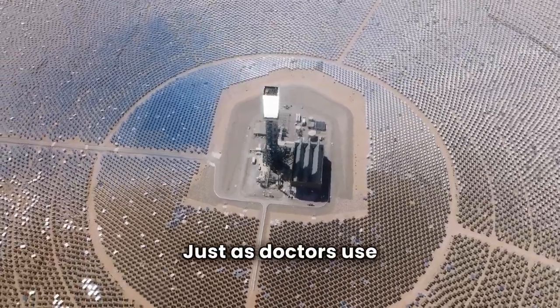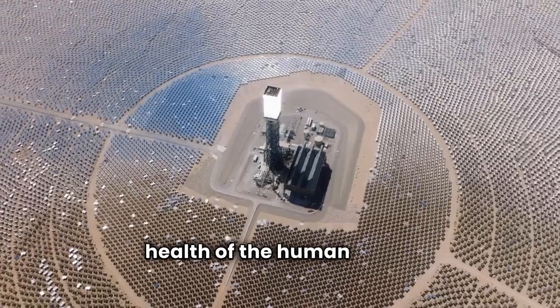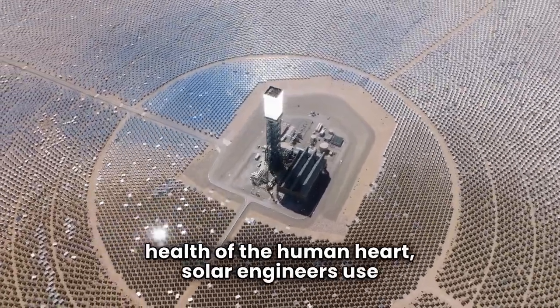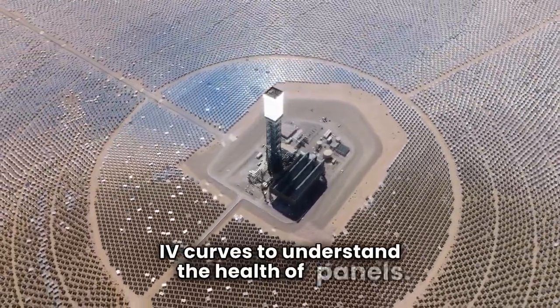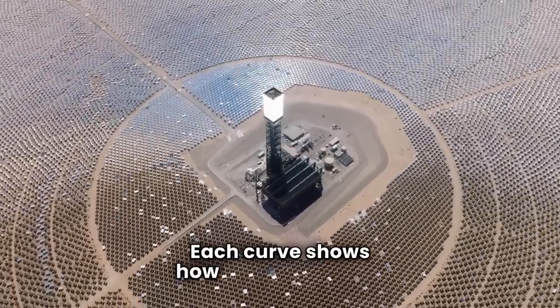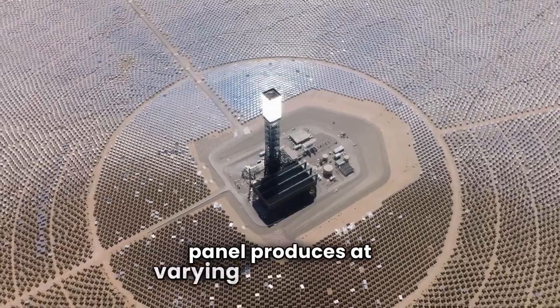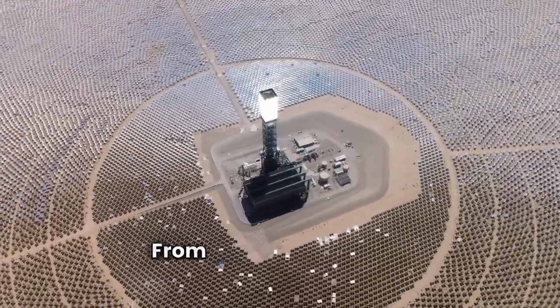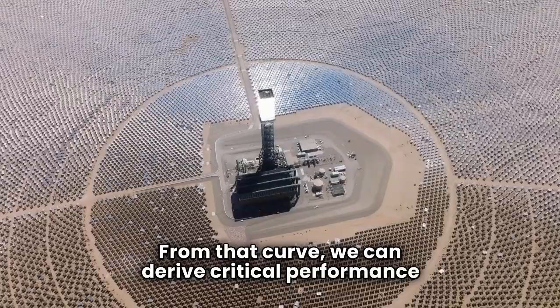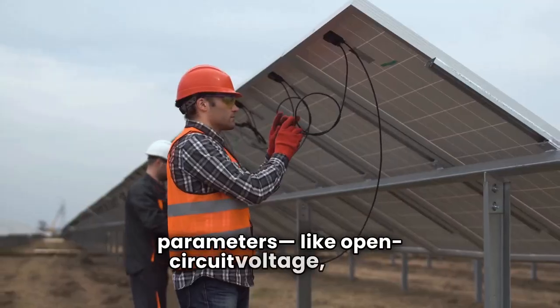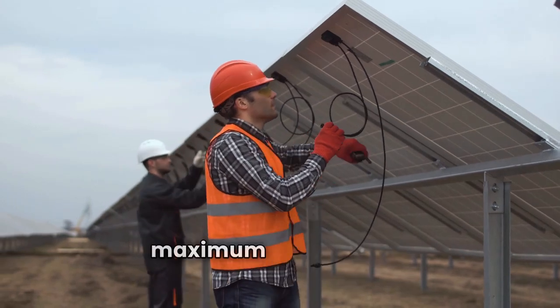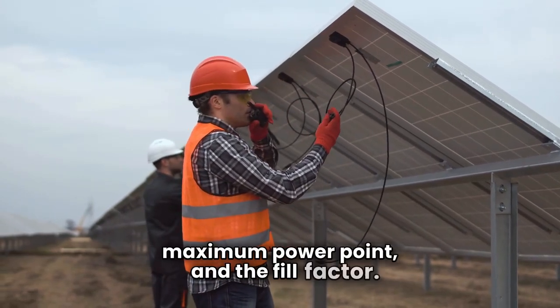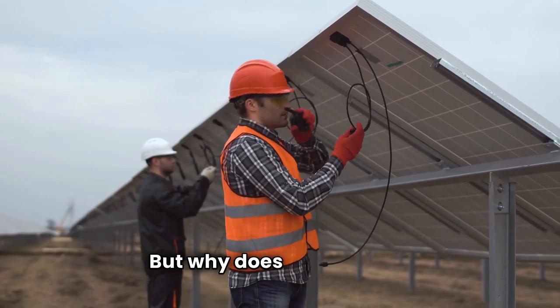Just as doctors use ECGs to understand the health of the human heart, solar engineers use IV curves to understand the health of panels. Each curve shows how much current a panel produces at varying voltage levels. From that curve, we can derive critical performance parameters like open circuit voltage, short circuit current, maximum power point, and the fill factor.